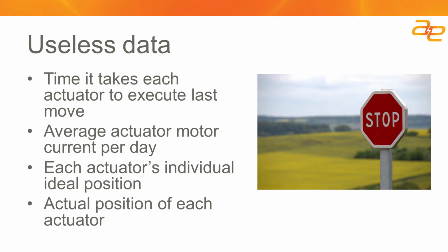I just want to see what the highest point is for each individual actuator. You don't really need to know each individual actuator's position. The most common thing is I've got 20,000 actuators on a site, so how do I make an HMI screen that shows me the position of everything? All I want is a list of the actuators that aren't pointing near where they're supposed to be. Don't tell me everything that's good, only tell me the things I need to pay attention to.